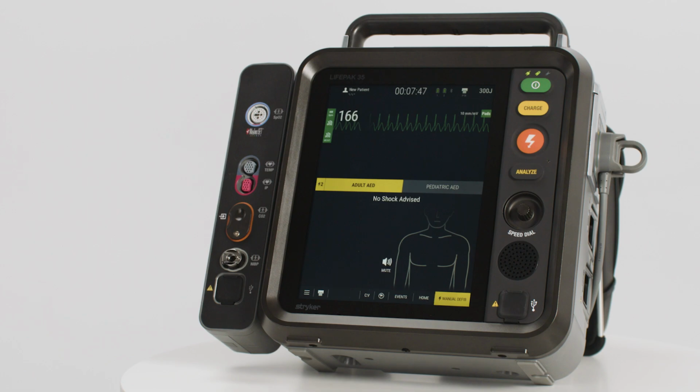If the defibrillator detects a non-shockable rhythm using CPR Insight, the No Shock Advised message will be provided before continuing into the next cycle of CPR time.